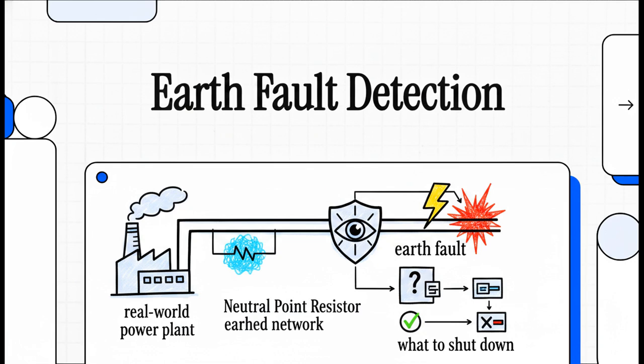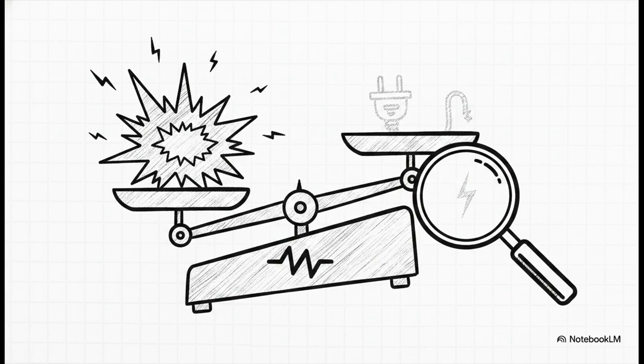Let's jump right in. Okay, let's dive into this by briefly tethering back to part 1. You'll remember that a neutral point resistor, or NPR, serves as this deliberate, calculated middle ground. By earthing a generator's star point through a resistor, we limit the fault current to a stable, moderate level. It totally prevents those violent, equipment-destroying current spikes you'd get in a directly earthed system. But it also stops the completely invisible faults you'd get in an isolated network.